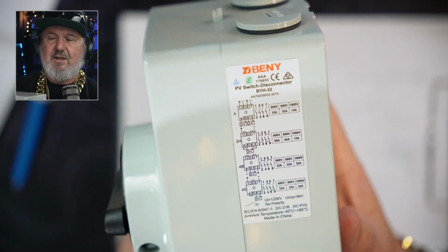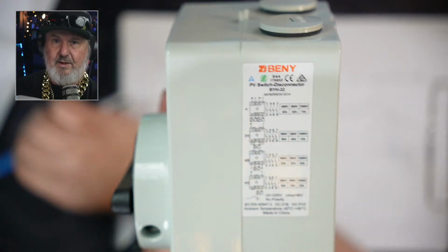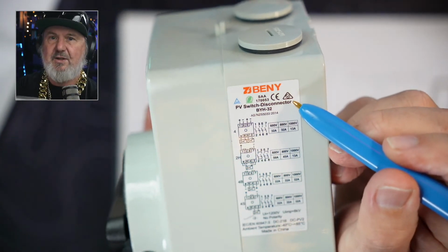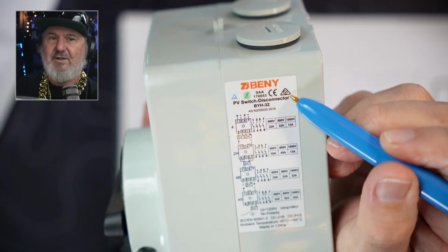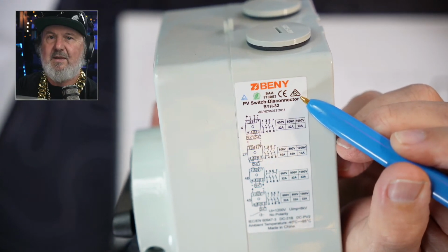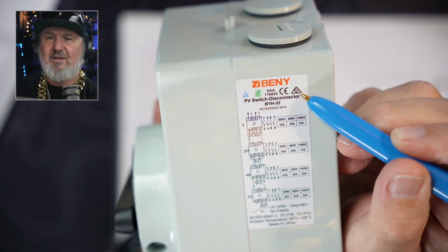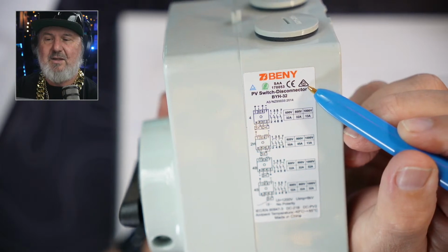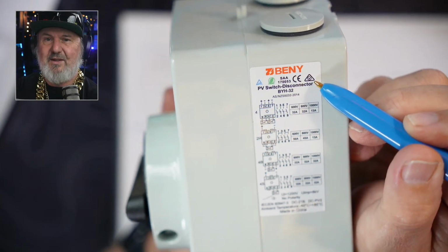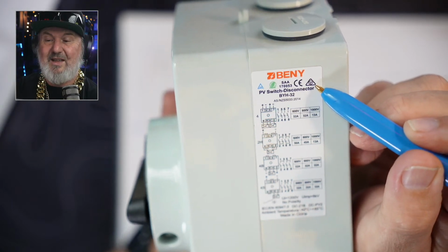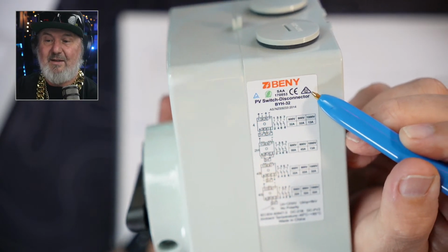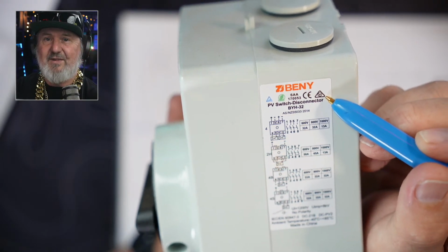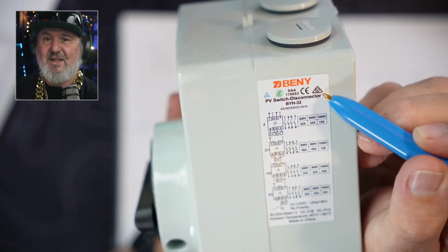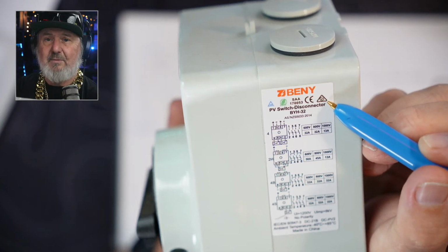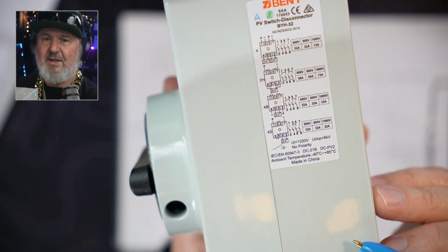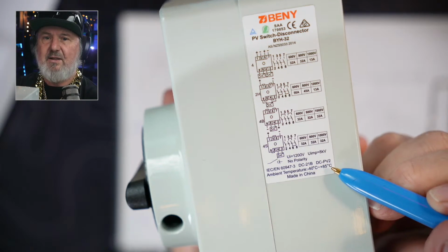But the thing I want to point out is that little symbol, see if I can do this with one hand and point with the other here. This is known as an RCM marking, Regulatory Compliance Mark. It's an Australian New Zealand Regulatory Compliance Mark, and it means it's actually been approved as a product for what it's deemed to achieve. So it's kind of like a guarantee that this is not just fluff. So this switch has met, for instance, IEC 60947.3. In fact, I think they even list that on the bottom here somewhere.